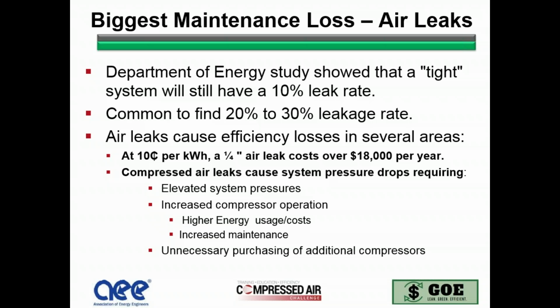a 10% leakage rate. The CAC likes to push to get between 5 and 10%, because again, as you fix leaks, other ones come about. And it's not uncommon to find a 20 to 30% leakage rate, sometimes as high as 50%. Air leaks cause efficiency losses in several areas. The leak itself, at 10 cents a kilowatt hour, a 1/4 inch air leak will cost over $18,000 per year.